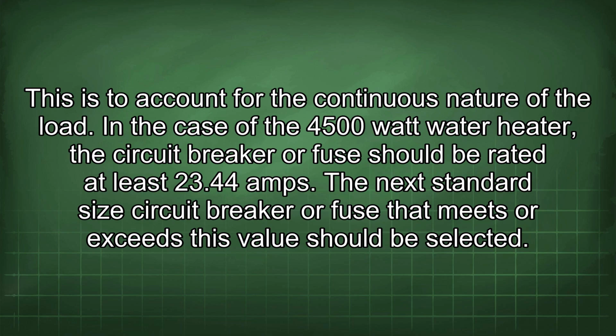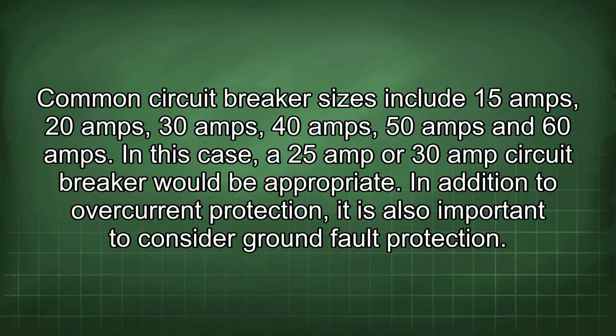In the case of the 4,500 watt water heater, the circuit breaker or fuse should be rated at least 23.44 amps. The next standard size circuit breaker or fuse that meets or exceeds this value should be selected. Common circuit breaker sizes include 15 amps, 20 amps, 30 amps, 40 amps, 50 amps and 60 amps. In this case, a 25 amp or 30 amp circuit breaker would be appropriate.